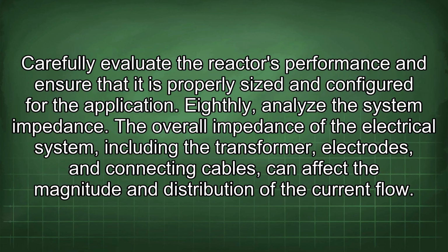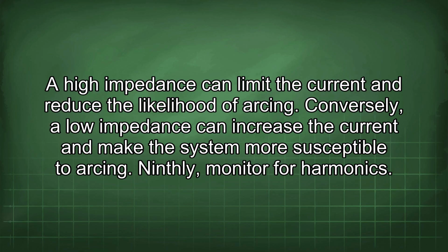Eighthly, analyze the system impedance. The overall impedance of the electrical system, including the transformer, electrodes, and connecting cables, can affect the magnitude and distribution of current flow. A high impedance can limit the current and reduce the likelihood of arcing. Conversely, a low impedance can increase the current and make the system more susceptible to arcing.